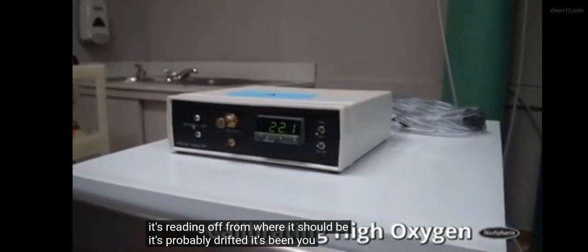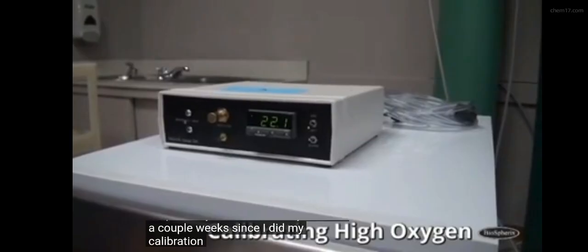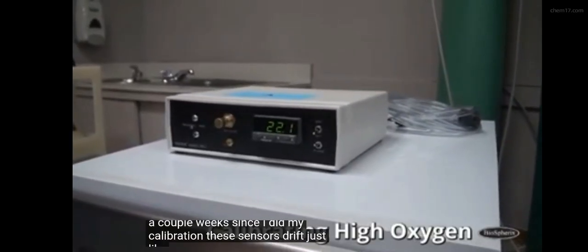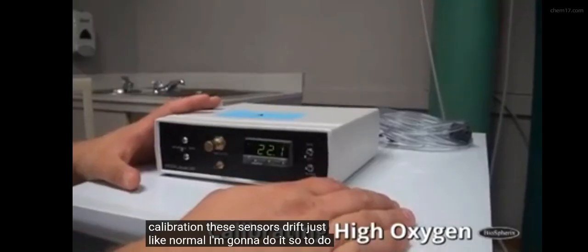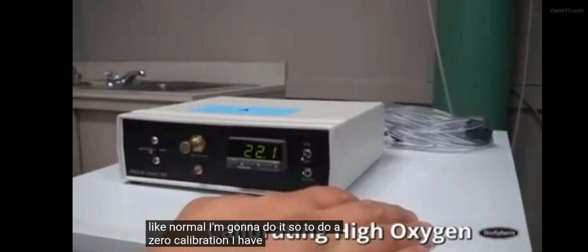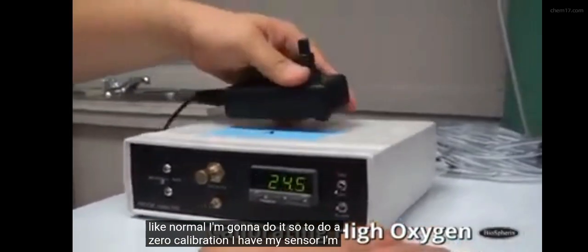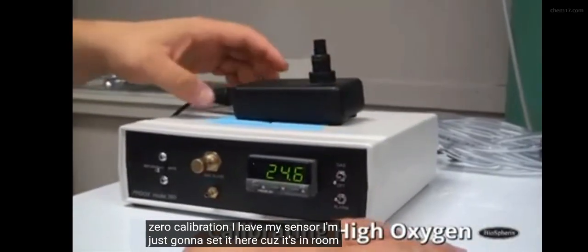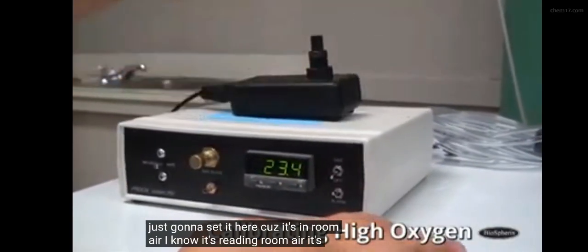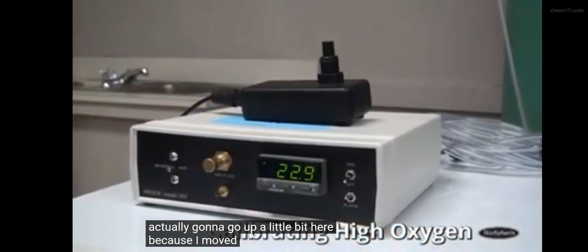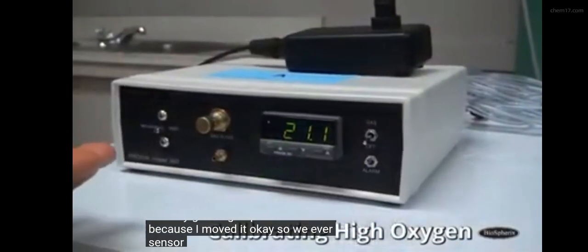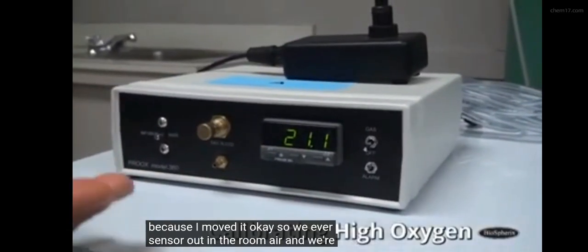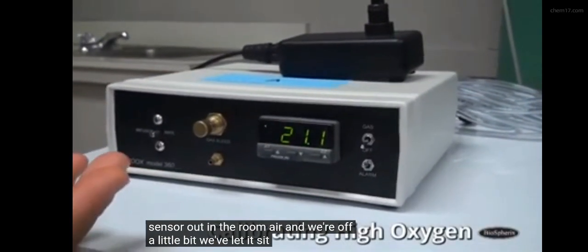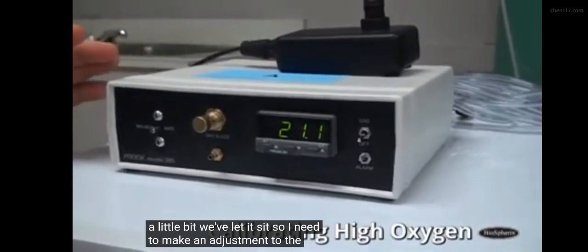It's probably drifted. It's been a couple weeks since I did my calibration. These sensors drift just like normal, so I'm going to do it. To do a zero calibration, I have my sensor. I'm just going to set it here because it's in room air. I know it's reading room air. It's actually going to go up a little bit here because I moved it. Okay, so we have our sensor out in room air and we're off a little bit. We've let it sit, so I need to make an adjustment to the zero.